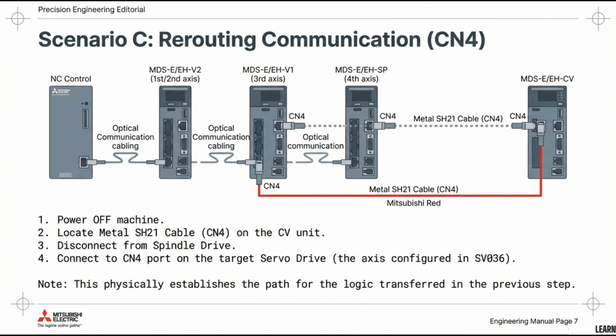The next step is rerouting communication with CN4. Power off the machine. Disconnect the metal SH21 cable on the CV unit from the spindle drive and connect it to the CN4 port on the target servo drive configured in SV036.